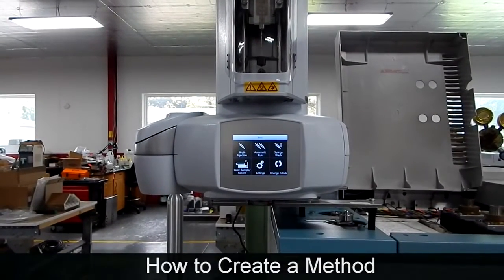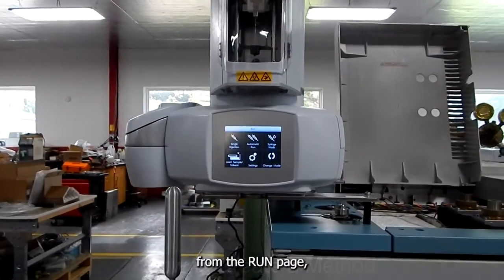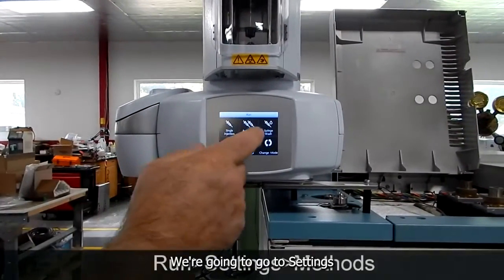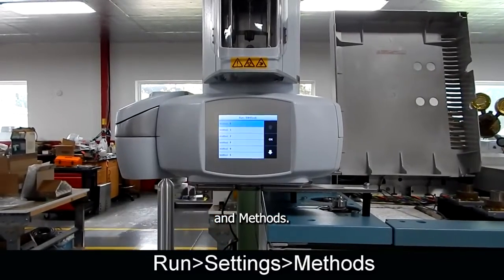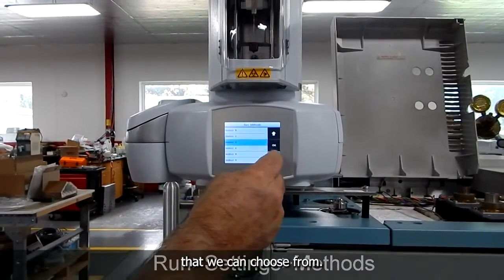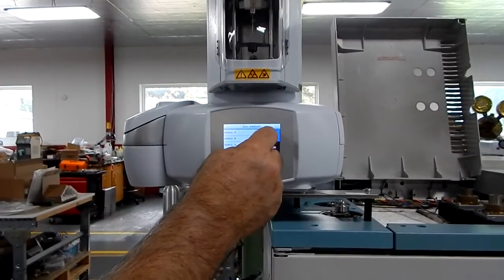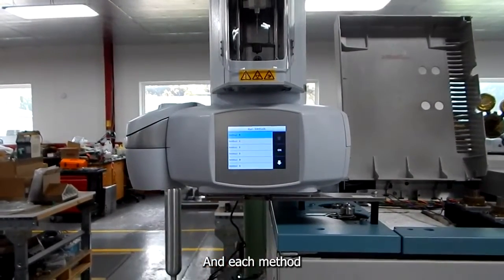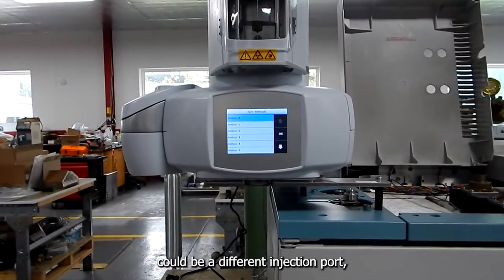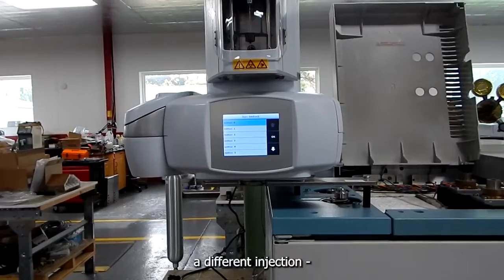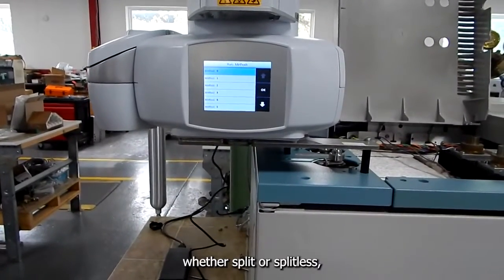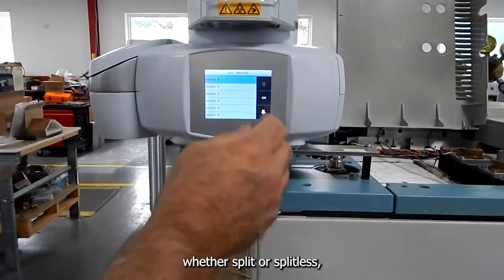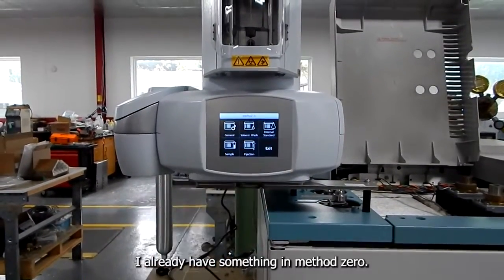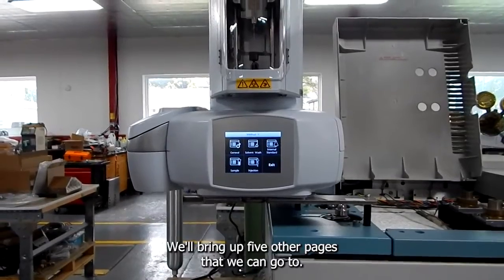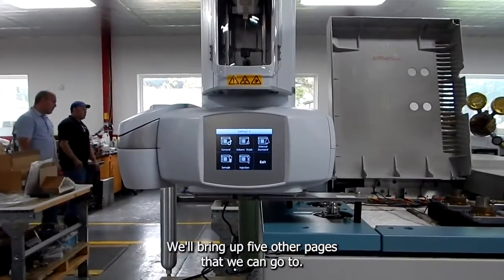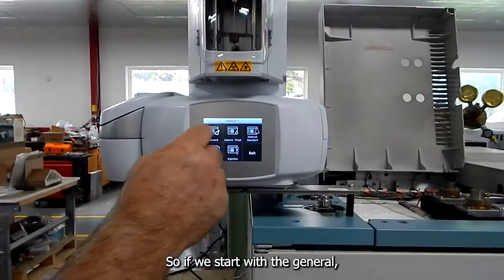Okay, to create a method, from the run page, we're going to go to settings and methods. And so there are 9 methods that we can choose from. And each method could be a different injection port, a different injection, whether split or splitless. And so I already have something in method 0. It'll bring up 5 other pages that we can go to.